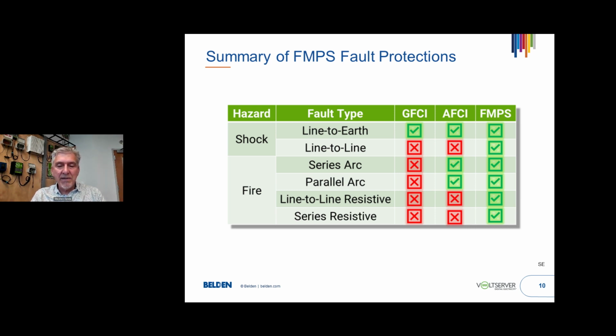All those things are now managed in a fault managed power system. You can look at the overall technology as taking something that's inherently dangerous. Today's technologies create a source voltage and current distributed into the circuit, and then external safety devices manage that circuit so it doesn't hurt somebody or cause a fault. In fault managed power systems, the source or dangerous conditions are managed by digital technology at the transmitter.